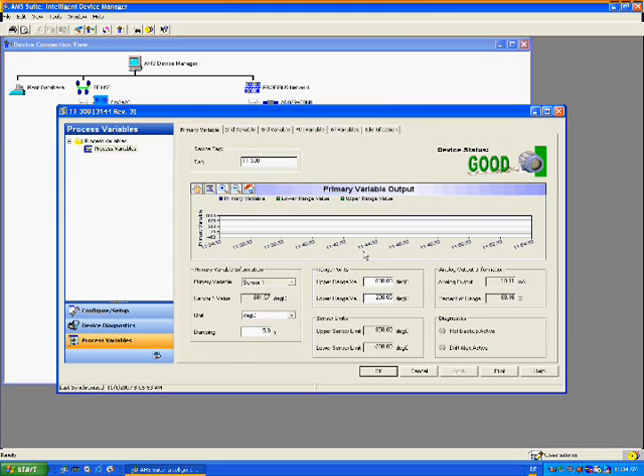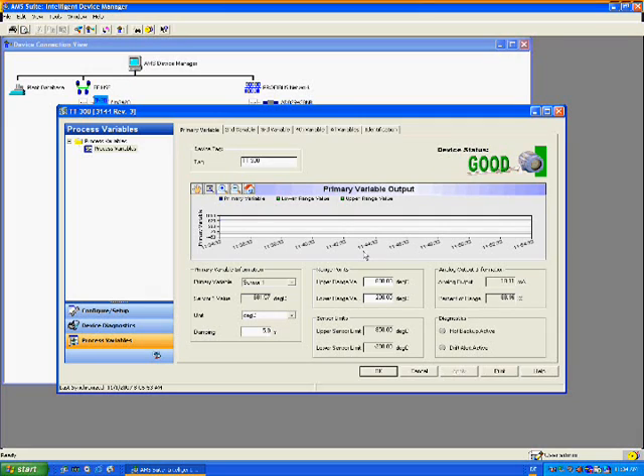In the top right corner, there is an image with a grey background, and it is conditional — that is, it changes with the status of the device. At the center of the page, the device manufacturer has decided there shall be a trend chart that contains three pens for primary variable, lower range limit, and upper range limit. Note that in this system, the trend chart has a toolbox with buttons to pan and to zoom. This toolbox comes from the system, so these buttons work the same way for any type of device, from any manufacturer, any version, using any protocol.